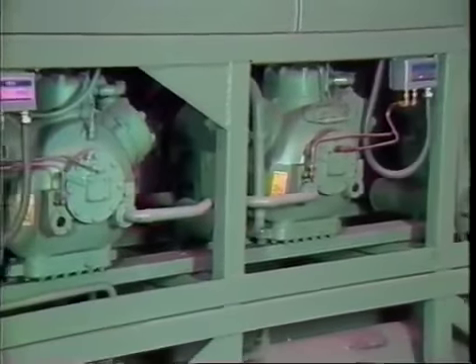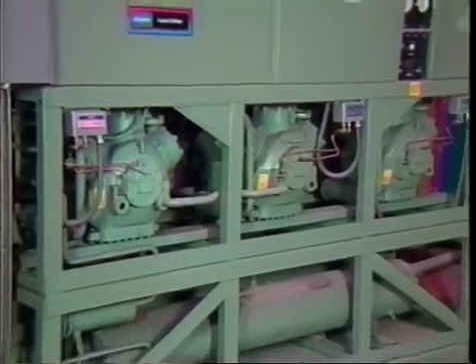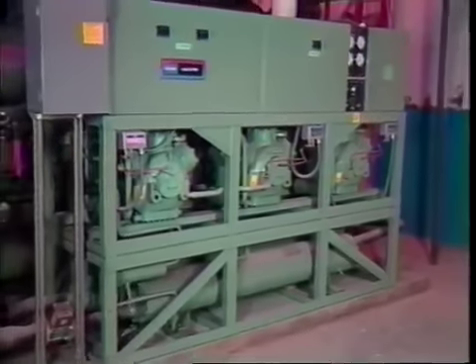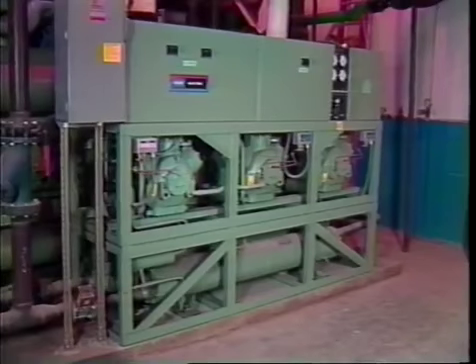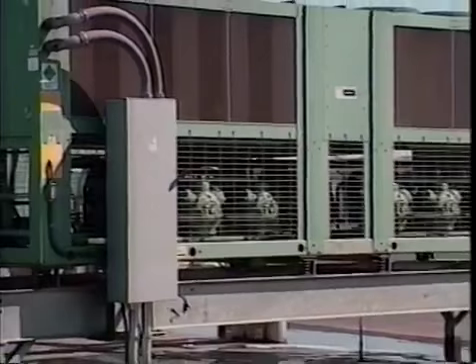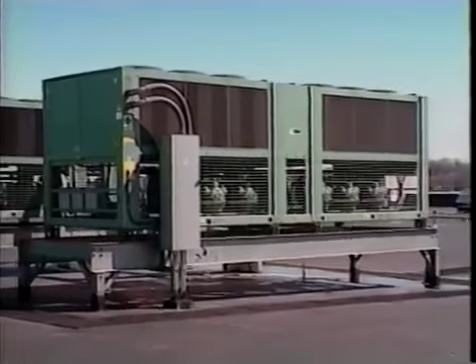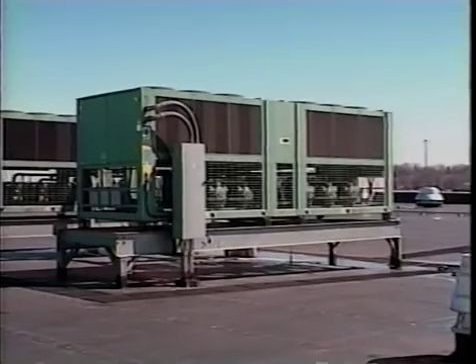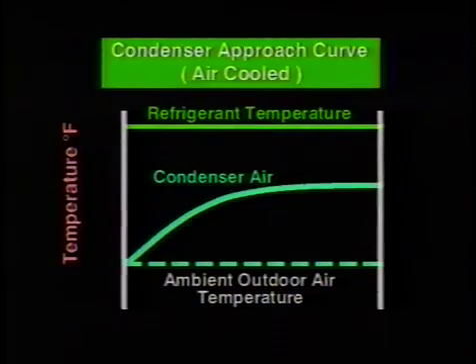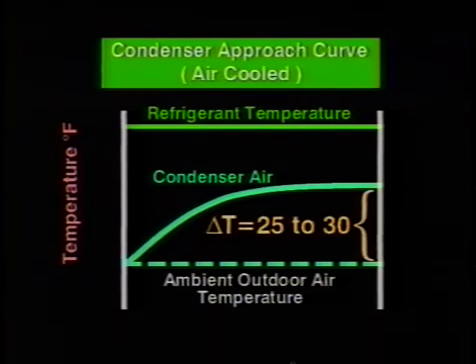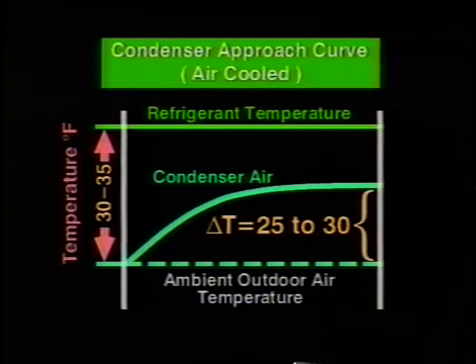The discussion up to this point has been directed toward reciprocating compressor chillers with water-cooled condensers. The same symptoms apply to chillers with air-cooled condensers, the only difference being that instead of working with condenser water in and out temperatures, we need now to be aware of the condenser's air in and out temperatures. Typically, at design full load conditions, a 25 to 30 degree rise is expected in the air temperature across the coil. The condensing refrigerant temperature should be about 30 to 35 degrees Fahrenheit above the ambient temperature at design full load conditions.